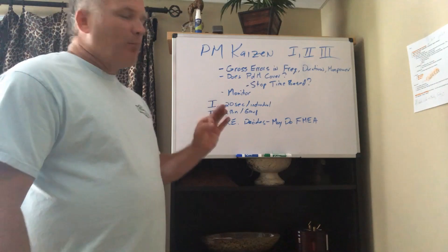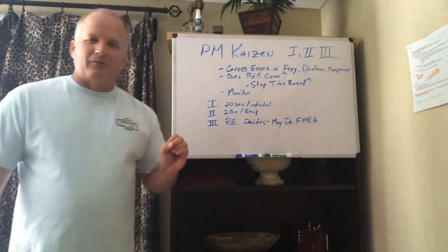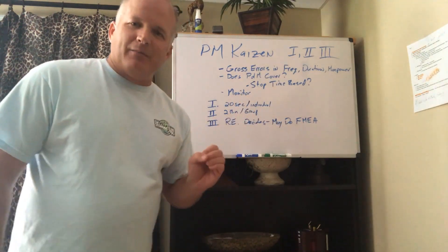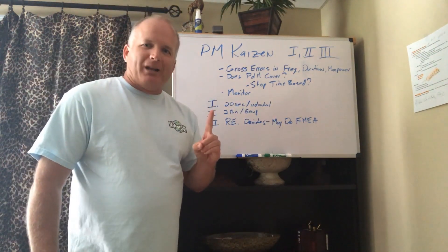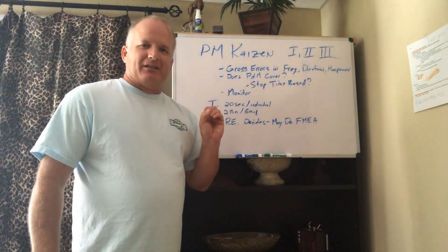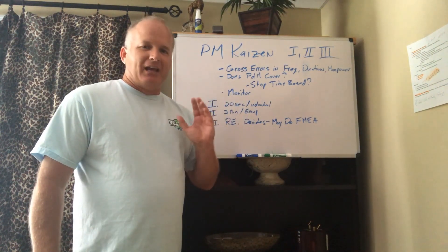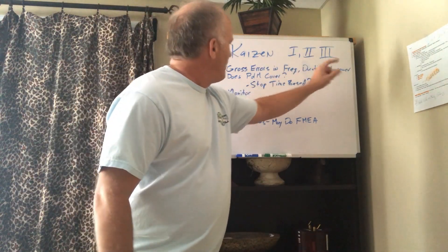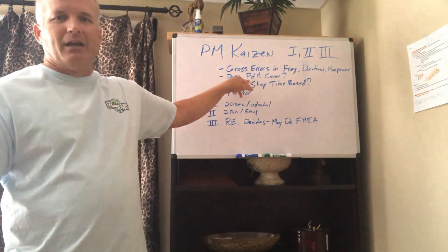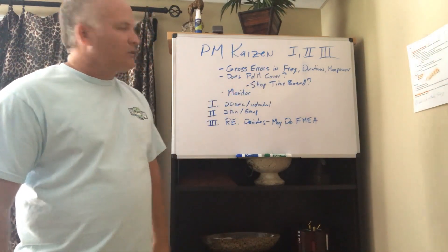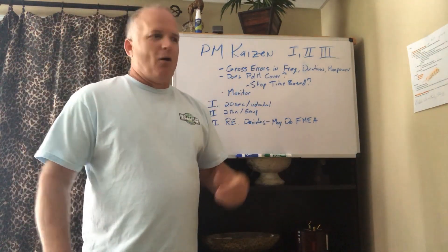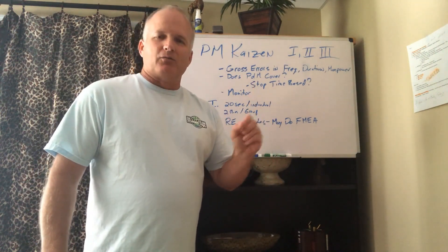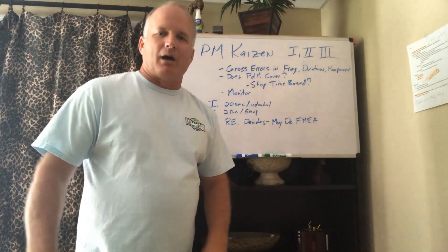Your simple action for this week from Lean Driven Reliability: conduct a PM Kaizen Level 1. That takes 20 seconds per PM. Look for the ridiculous in frequency, duration, and manpower. Does PDM cover it? Make a quick decision on whether you should continue time-based work. Why change oil once a month if you're doing oil analysis? There's a lot of money here. Remember, if you like what you're seeing, hit subscribe. Thanks.